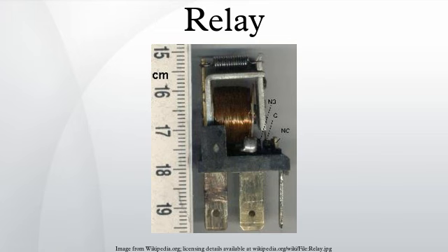Time delay functions. Relays can be modified to delay opening or delay closing a set of contacts. A very short delay would use a copper disc between the armature and moving blade assembly. Current flowing in the disc maintains the magnetic field for a short time, lengthening release time. For a slightly longer delay, a dash pot is used. A dash pot is a piston filled with fluid that is allowed to escape slowly.